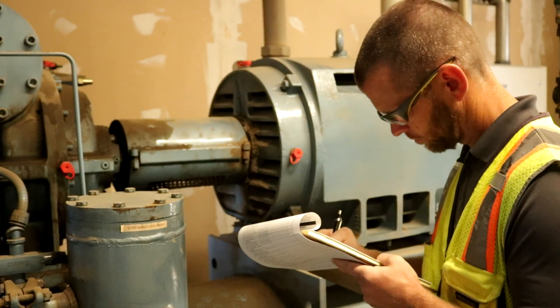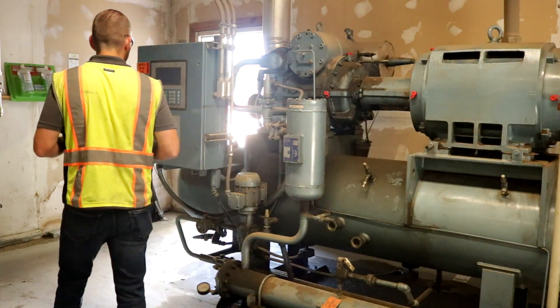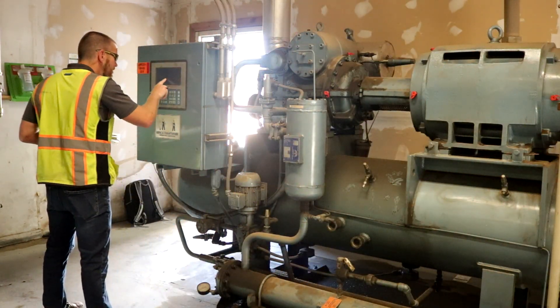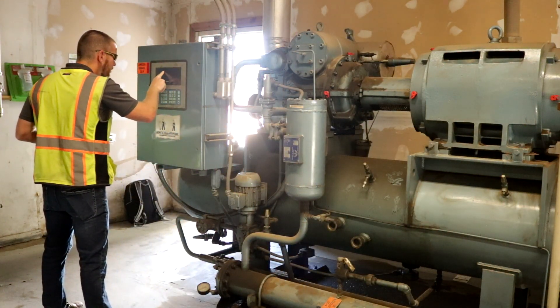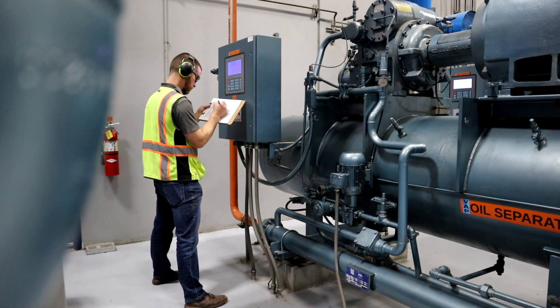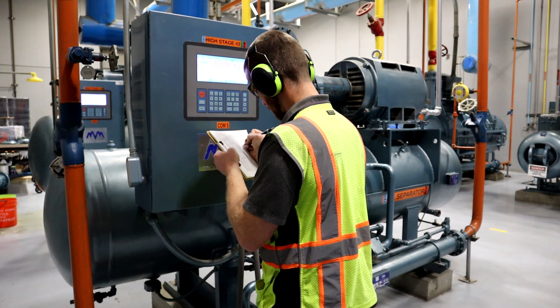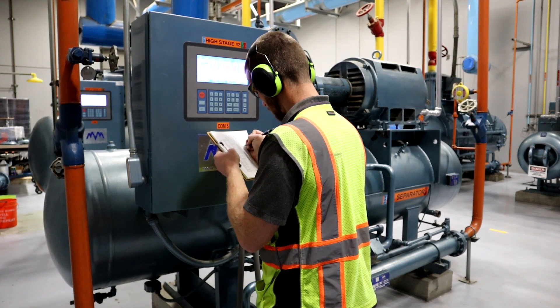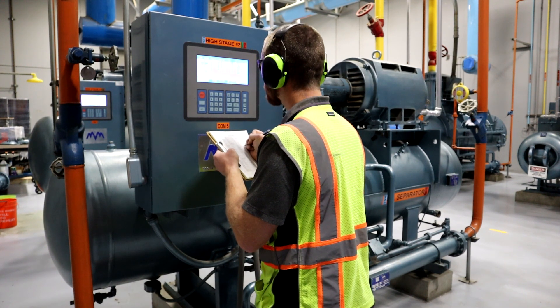As a result, refrigeration systems with very low evaporator temperatures cannot operate efficiently using a single stage of compression. Engineers address this by employing a two-stage system in which compression is divided between two different compressors that are in series with each other.